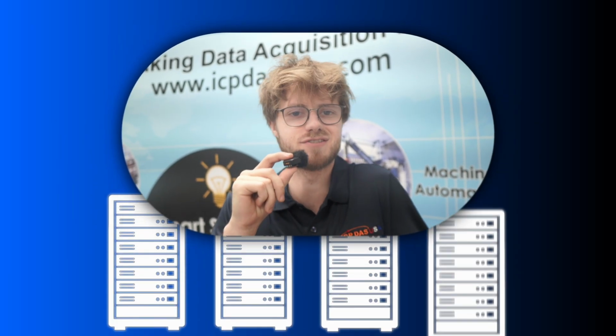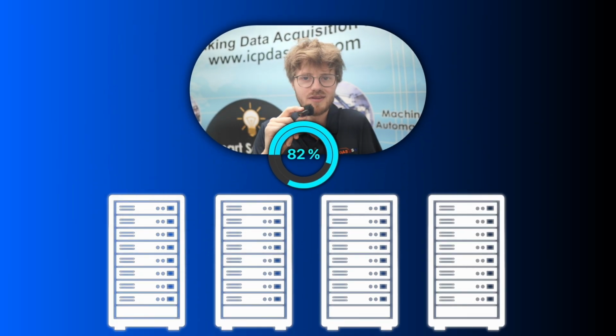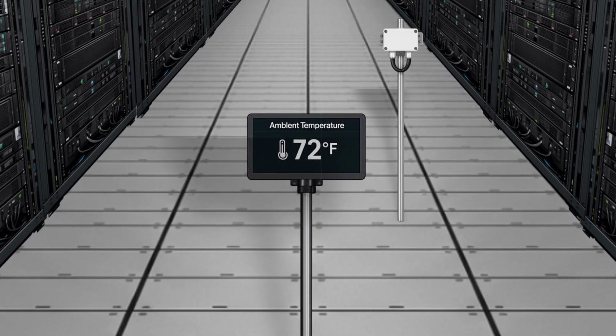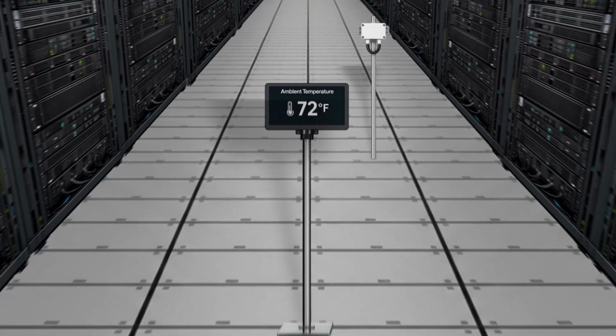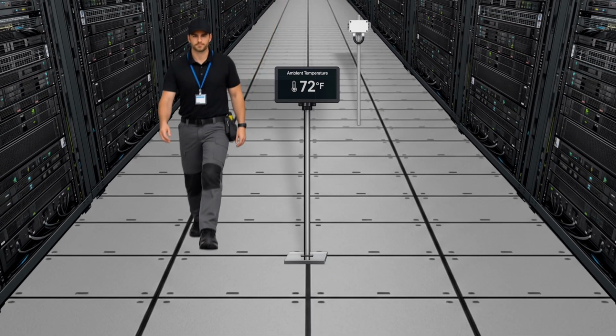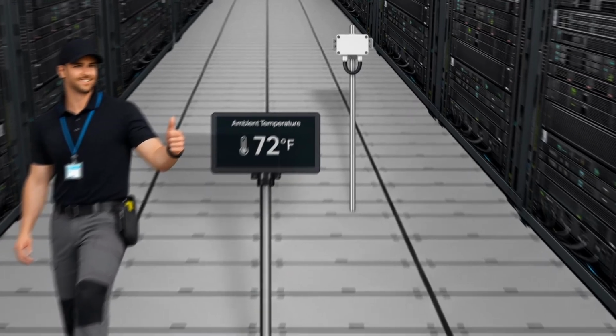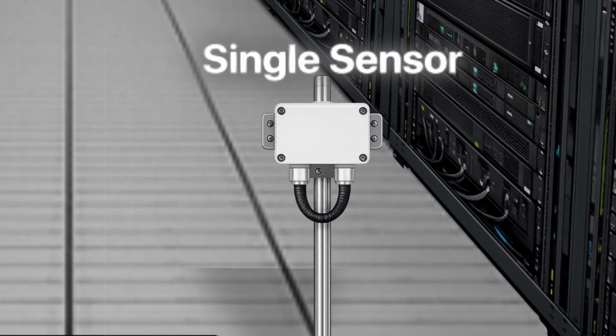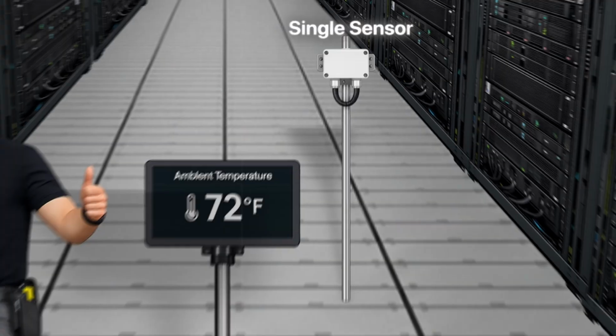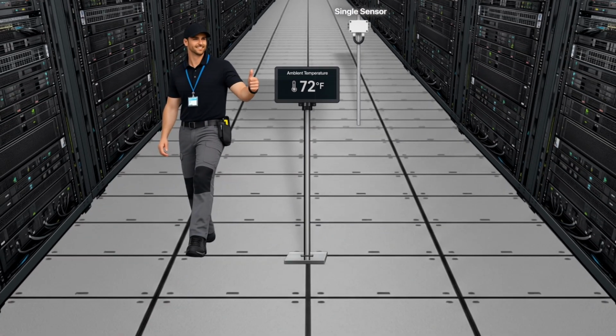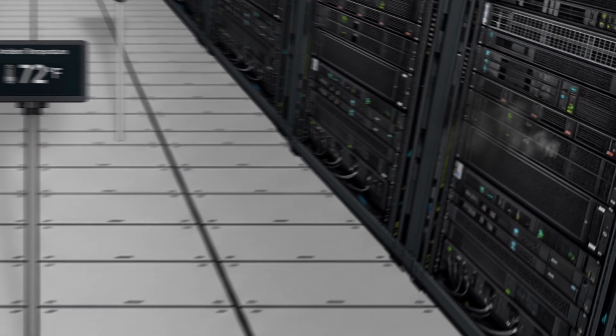Most data centers have some kind of temperature monitoring, but they almost always share the same problem. You see, there's a number on a dashboard somewhere showing the ambient air temperature in the room, and as long as that number looks reasonable, the assumption is that everything is fine. But that number is measured from a single sensor, and it only tells you the average temperature of the air in the room, so it doesn't tell you what's happening inside of your racks. That distinction is where equipment fails.